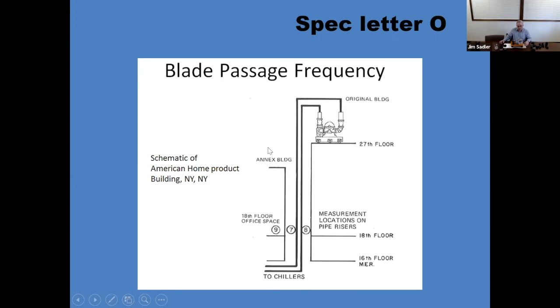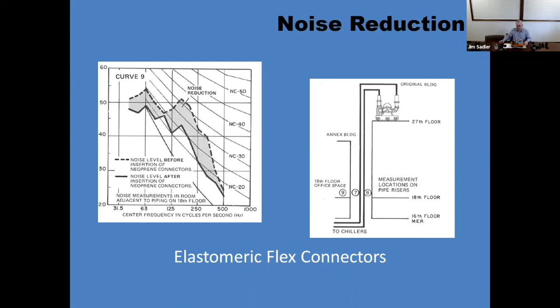By introducing those elastomeric rubber connectors, you reduce the noise by 10 decibels on the 18th floor. The reason it works is that the elastomeric connector can expand volumetrically with that pulsation, and it knocks out that standing wave. Again, it's not traveling through the pipe wall, it's traveling through the water column.